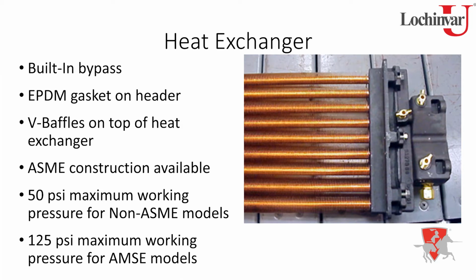But in the saltwater application, you do have the option to go to what's called a copper nickel, which is 90% copper, 10% nickel on the tube. It's a little bit harder tube. So in those saltwater applications, you want to protect the heat exchanger, go to a copper nickel with the bronze headers, you're going to have the max safety at that point. Now the picture that you see here, the header is actually upside down, so you can actually see the drains on the bottom of the heat exchanger, so you can drain it.